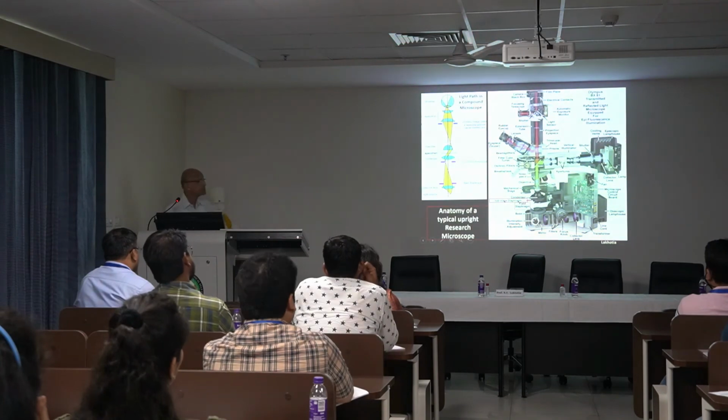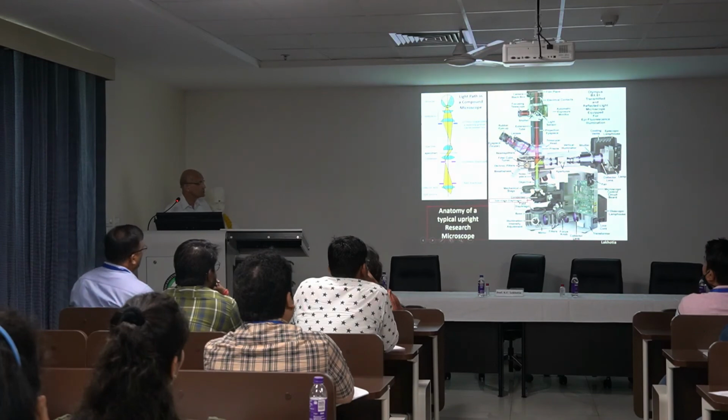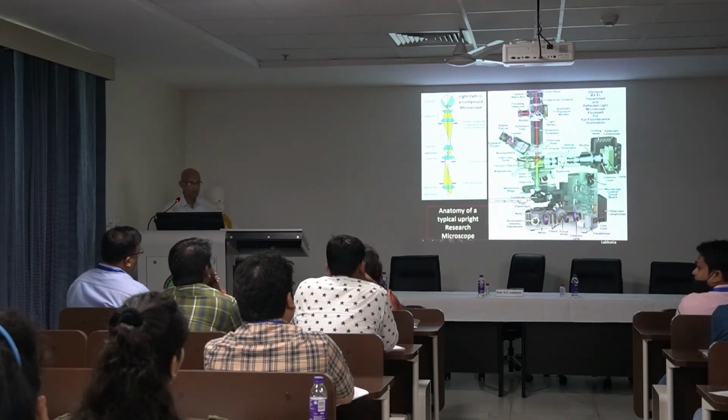camera digital system. For fluorescence, we have a mercury lamp or some other arc lamp on the upside here, from which light comes. There is a reflector here that sends the light down the objective, and then internal reflection will send the fluorescent light back to the objective, and then it passes the barrier filter. I'll come to this part later, and then you see the object, the fluorescence, and so on.